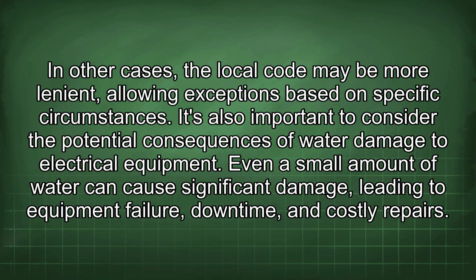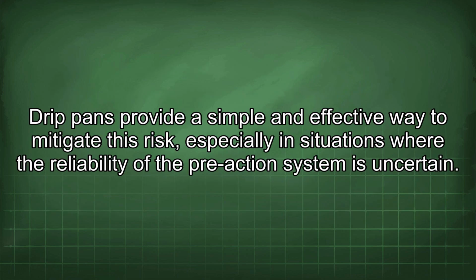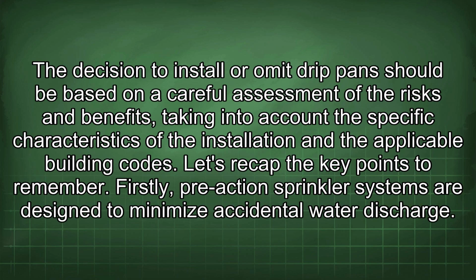It's also important to consider the potential consequences of water damage to electrical equipment. Even a small amount of water can cause significant damage, leading to equipment failure, downtime, and costly repairs. Drip pans provide a simple and effective way to mitigate this risk, especially in situations where the reliability of the pre-action system is uncertain. The decision to install or omit drip pans should be based on a careful assessment of the risks and benefits, taking into account the specific characteristics of the installation and the applicable building codes.